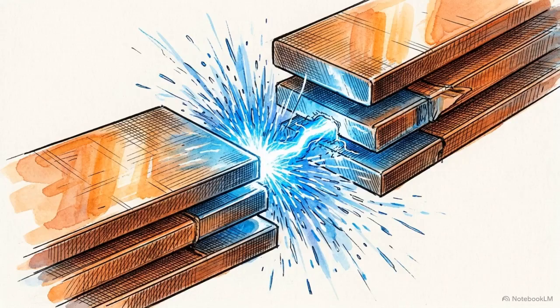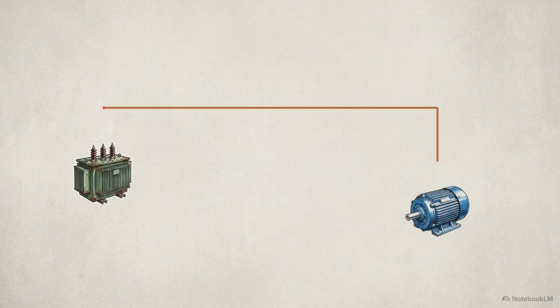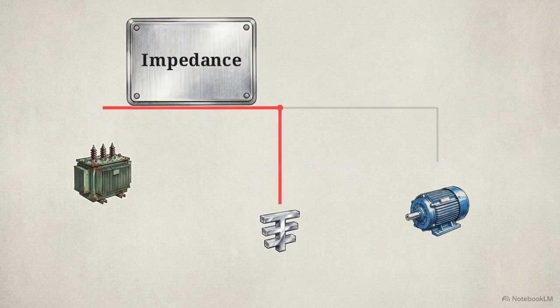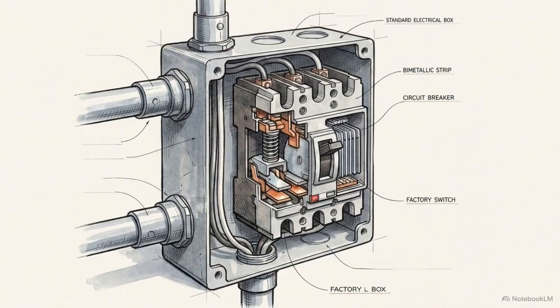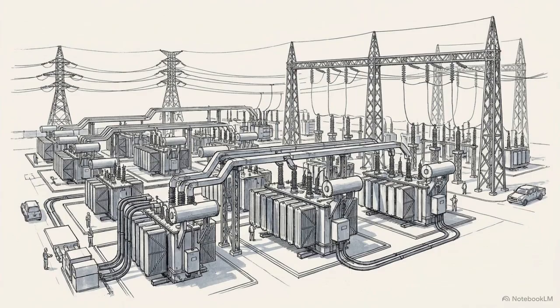Short circuits are violent electrodynamic events. Because the downstream load is bypassed, the only factor limiting the energy is the physical impedance of the wiring, located upstream of the fault. A protective device sized solely to handle the normal demands of the facility is completely blind to the terrifying volume of energy the upstream grid can force through it.